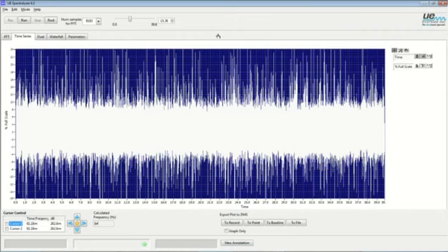The second thing I need to look for is the other characteristic of a tracking event, and that has to do with how often it is taking place. In other words, if I were to break it down to one electrical cycle, within that 16 millisecond period, how many times does energy discharge on that sine wave?